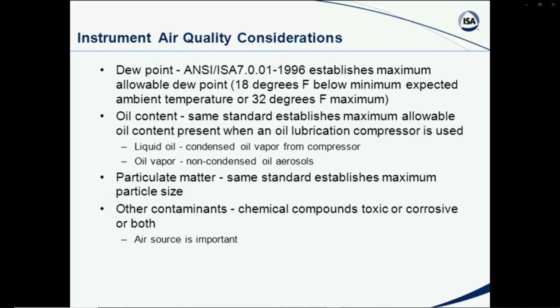And also, along the line of instrument air quality, I think we need to be aware, and there might be some questions of a practical nature dealing with whether we just take any kind of air that we can get, or whether we have requirements for that. Well, there are requirements for air quality as dealing with instrumentation, control valves, I/P transducers, pneumatic valve positioners, local pneumatic controllers. There's an ISA standard, I believe it's ISA-7, that establishes a maximum allowable dew point. In other words, dew point is the temperature where condensate begins to form out of the vapor. And if you have a dew point that's too high and the vapor begins to go into a liquid state, as that temperature continues to drop, you can freeze up and have devices malfunctioning and not working properly.